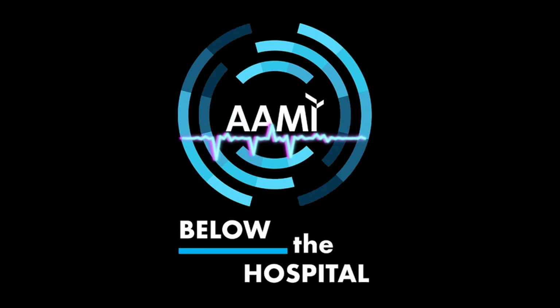of sterilizing. The disadvantage to X-ray is it requires a lot of energy. Somewhere between 6 and 12%, depending on the irradiator, of the energy you put in comes out as X-ray photons, which means it takes a lot of energy, and by far most of the energy you put into a piece of X-ray equipment goes off as heat. So you lose that as heat, which is not beneficial to the sterilization process, the way we're setting it up. So electron beam does not have that conversion issue of converting energy to electrons, but it does have the issue of not having as good a penetration.